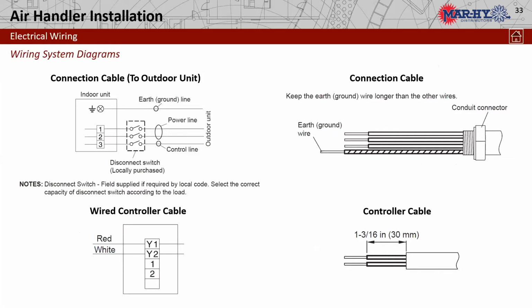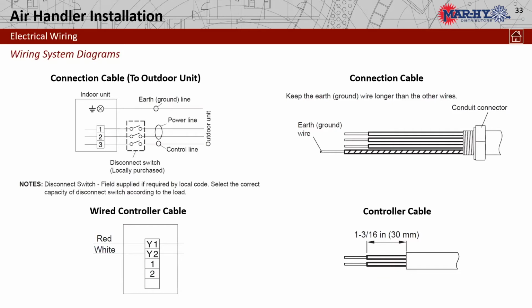So there's our indoor unit from the outdoor unit, basically 1, 2, and 3. Now they're showing a disconnect. There again, as with mini splits, we do not want a disconnect, not unless it is mandated by code, which would have to be a commercial application. But most of our applications, we will not require a disconnect. So it should be a straight run from the outdoor unit to the indoor unit. And there again, they're showing Y1 and Y2 as our low voltage connection, our 2-wire low voltage to the thermostat.